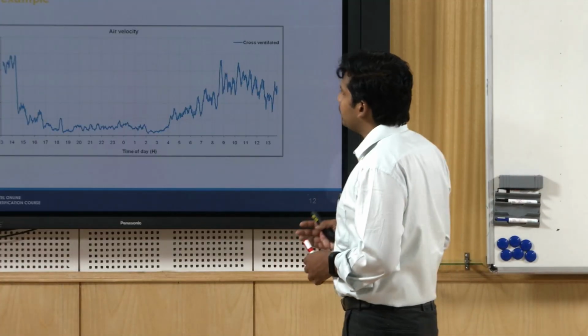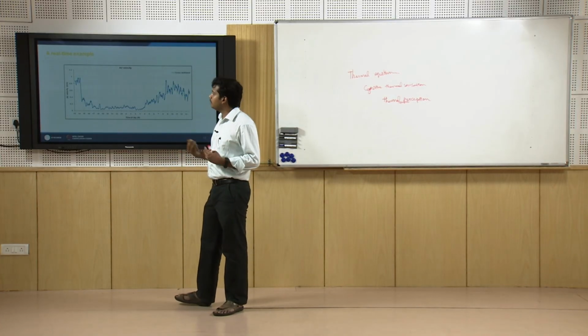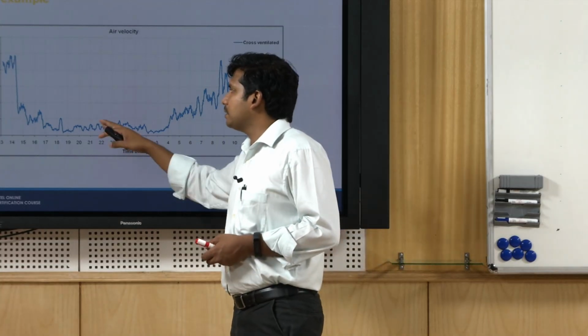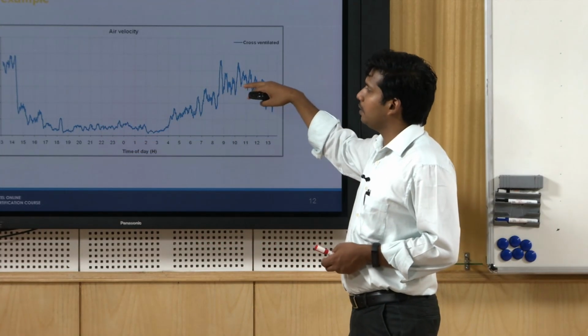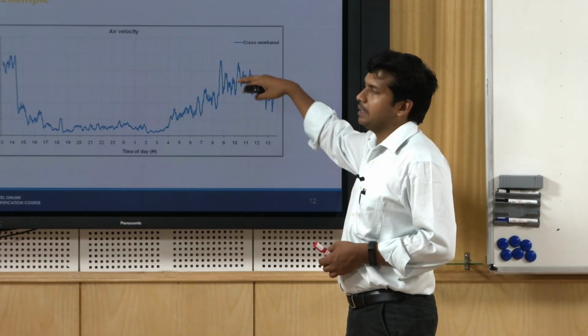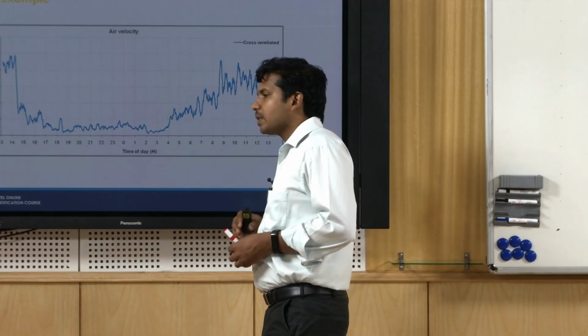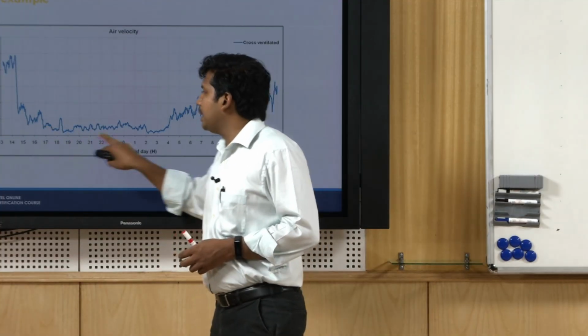In a nicely cross ventilated space, where two opposite facades have windows and are well ventilated, you may be able to expect somewhere around 0.2 to 0.3, or sometimes, when it is really well ventilated, around 0.6, 0.7 meter per second air velocity through natural ventilation. Again, it is not a consistent airflow that you can expect, so it may vary with time.